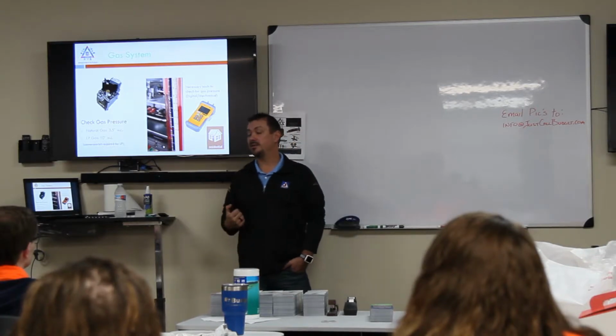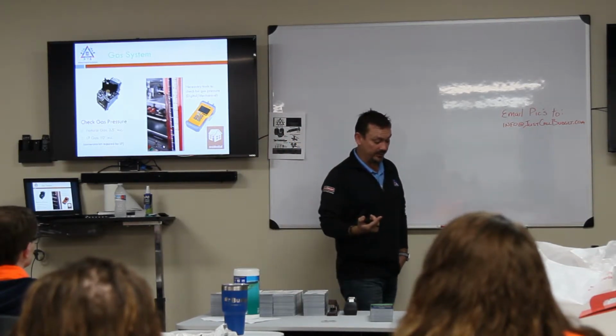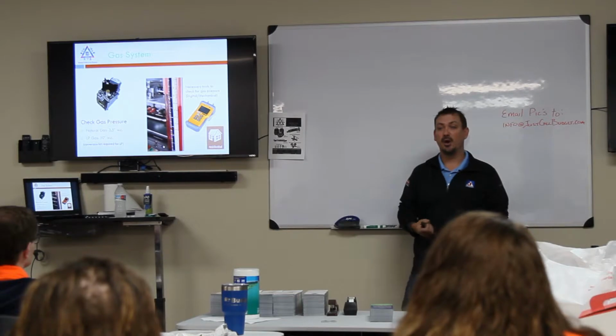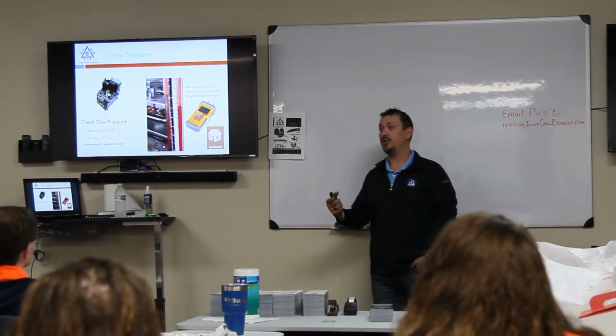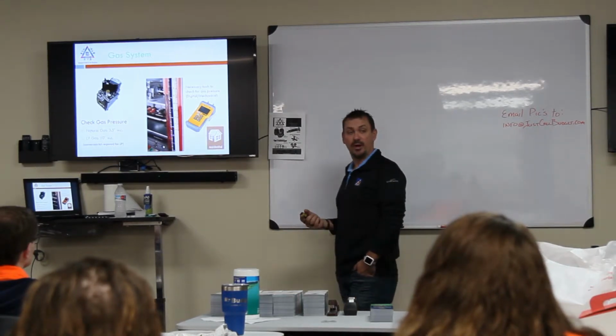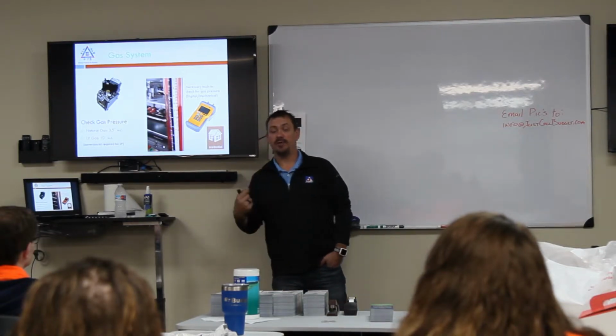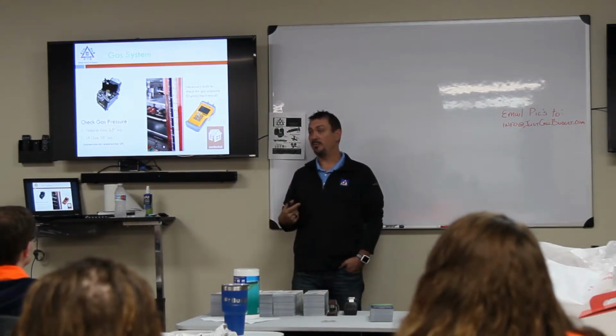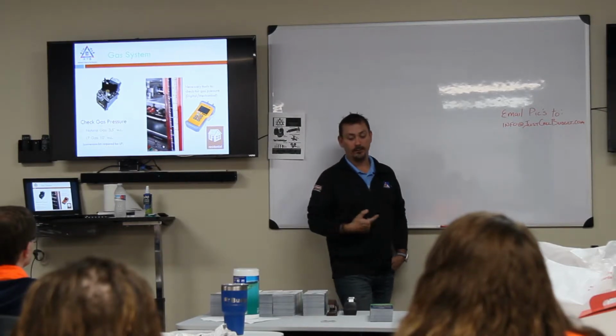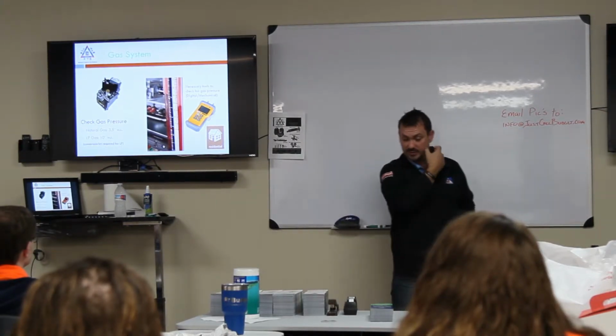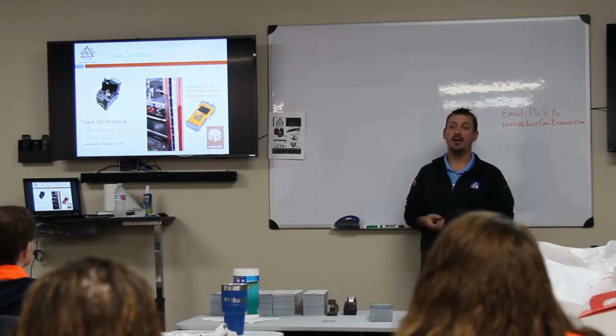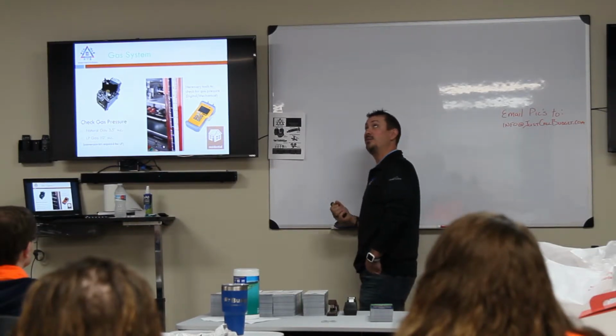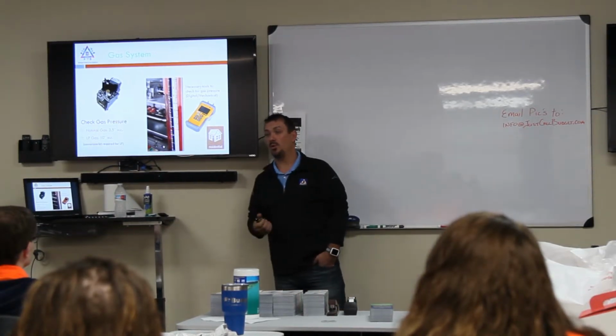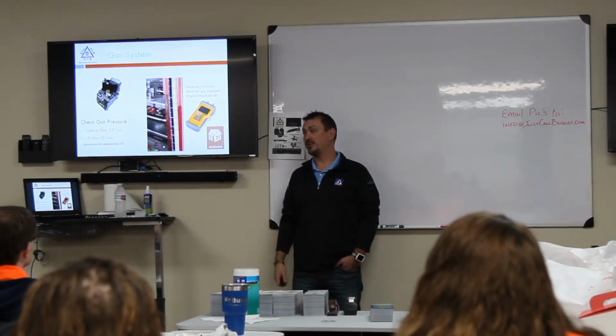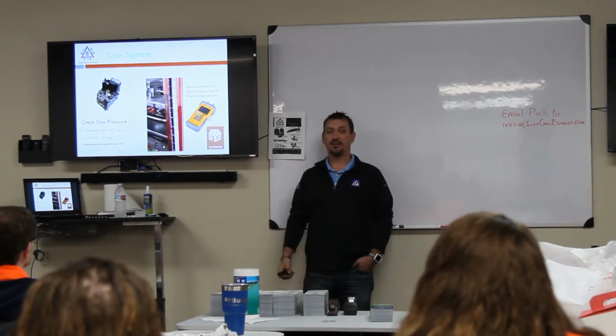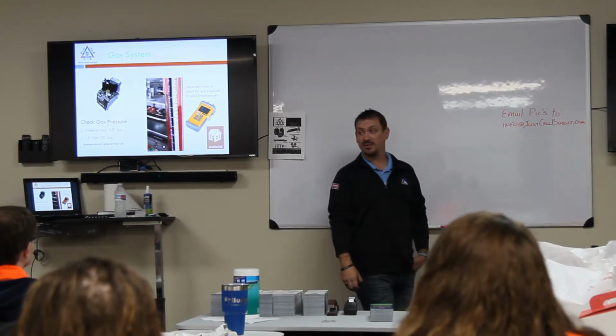And that's one of the things I like to talk about, is how a combustion analyzer can help retain or gain service contracts, if you guys use those. You get there and you'll check the efficiency of the equipment before you start. And we did this with one of the manager's houses. We checked the efficiency of the equipment before we started, and it was running under. It was an 80% efficient furnace, and it was only 6 years old, and it was running under 70% efficient. It was running at 68.5% or something like that efficiency. It was only 6 years old.